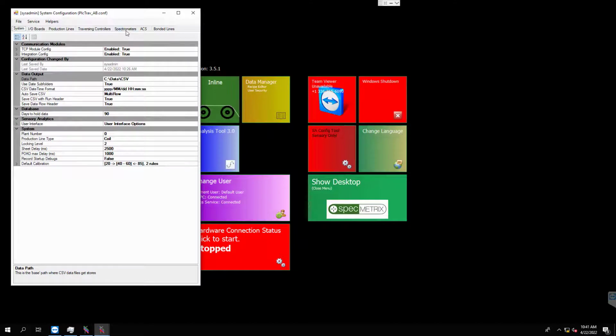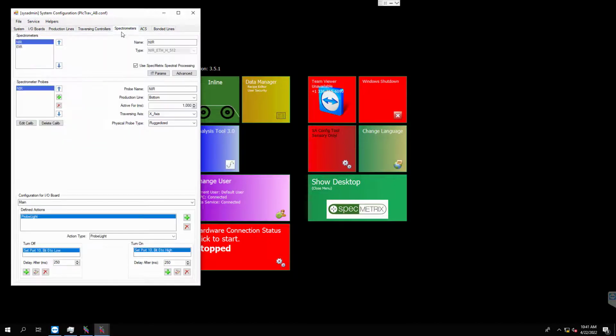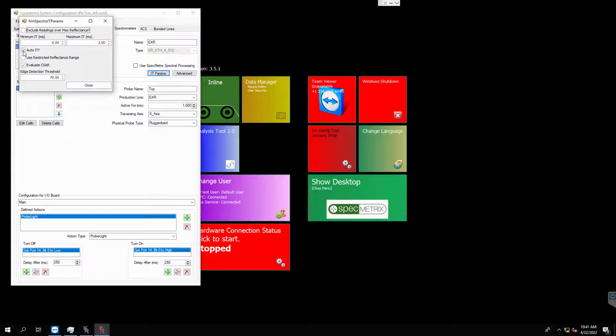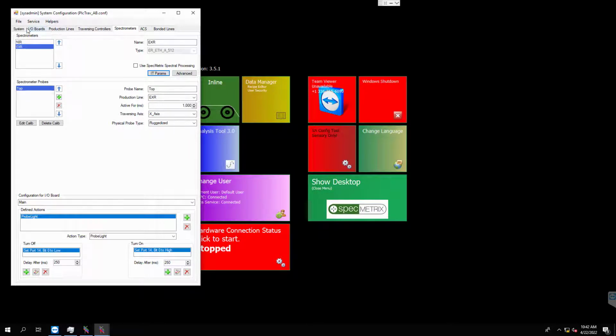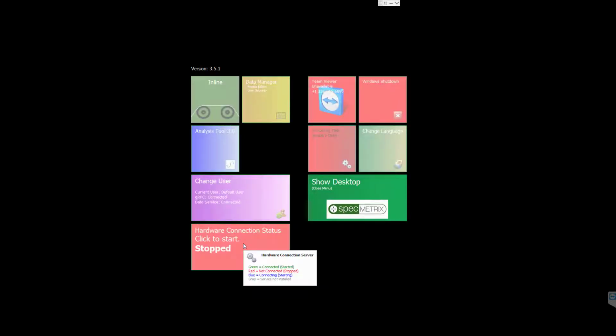Once the configuration tool is visible, select the Spectrometers tab. Select the first spectrometer which needs to be set up, click on the IT params, and uncheck the Auto IT checkbox. If the spectrometer type begins with EXR, the maximum IT should be 2.0. For NIR and VIS, it can be 5.0. Close the IT params pop-up, then click File and Save. Do not close the configuration tool as we will need it after we have adjusted focus.